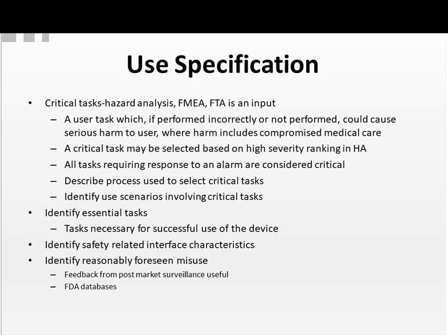In your specification, you should explain the process of how you selected these critical tasks. What was your criteria or your rationale for identifying critical tasks? You identify the use scenarios involving the critical tasks. So each critical task should have use scenarios related to it.